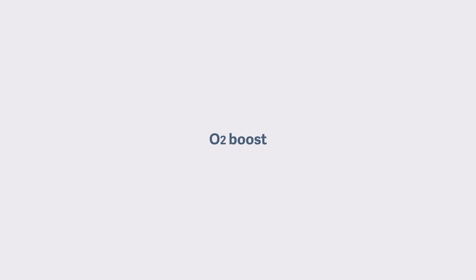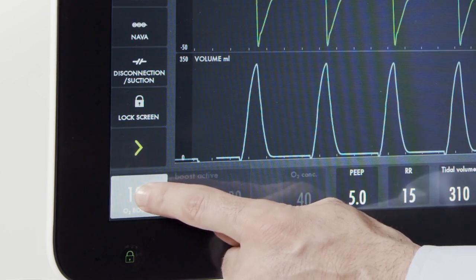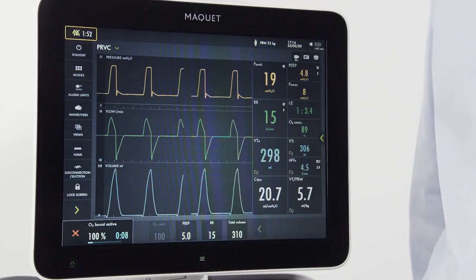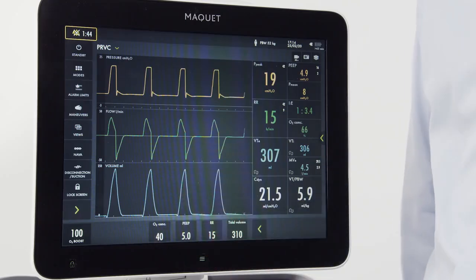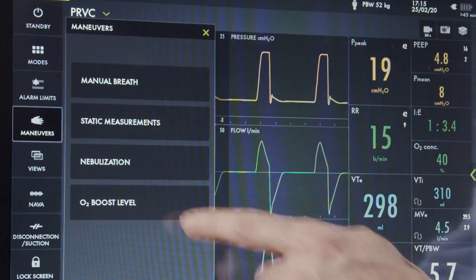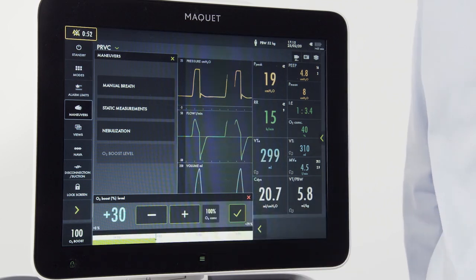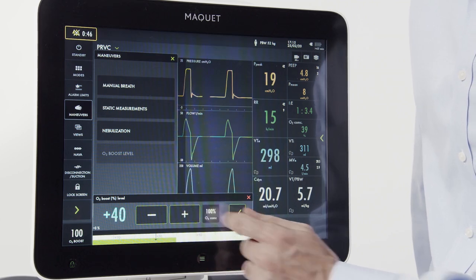To deliver a set increase in oxygen to your patient, note the button on the left bottom corner. When I press and hold it down, I've now activated a 1 minute O2 boost, and I've also activated alarm silence. To cancel the O2 boost, I simply press the red X. The O2 boost in this instance was set to deliver 100%. If I want to adjust that to an incremental increase, I can easily do that by going to the maneuver screen and pressing the O2 boost level button, then pressing the 100%. Now my O2 percentage is lit up and I can adjust the desired level for oxygen increase.